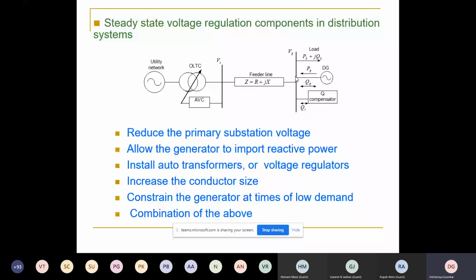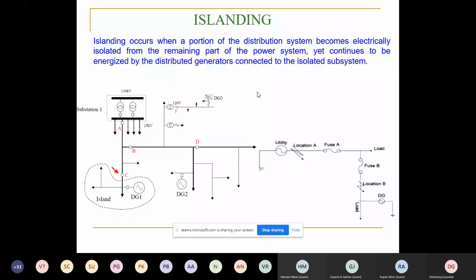Of course, a lot of research is required. Another important thing is islanding. As you know, when DGs are connected in a particular feeder and suddenly a fault happens somewhere else, the circuit breaker sees the fault and may separate out. Once it's separated, the DG is still in operation and it tries to feed the load.